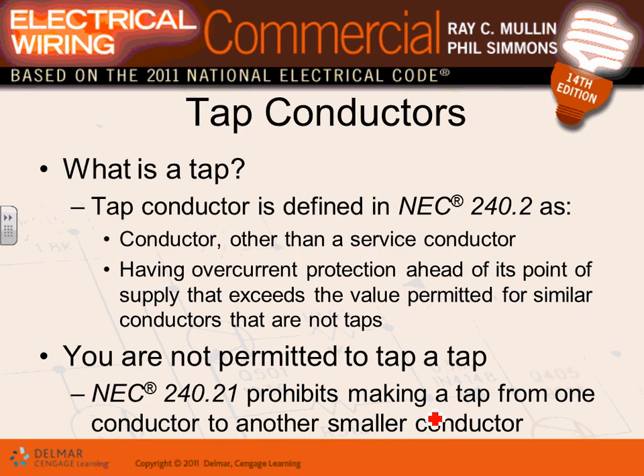I'm going to go over, guys, the tap rules, conductor taps. The NEC code book says that if you have a 20 amp circuit here feeding your beautiful light here, this conductor cannot be more than number 12, right? So you have to have an overcurrent device at the point where the conductor receives its power, right here. That's typical, almost 99% of the time. There is an exception for this. They call them taps. We'll talk about the taps.